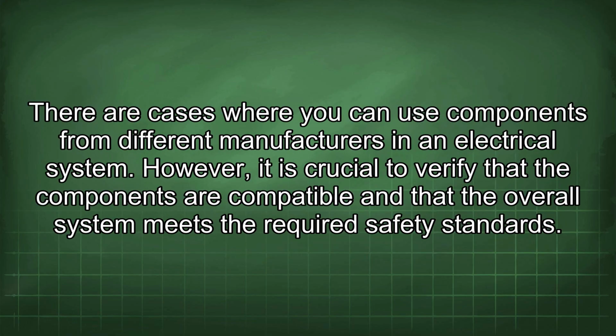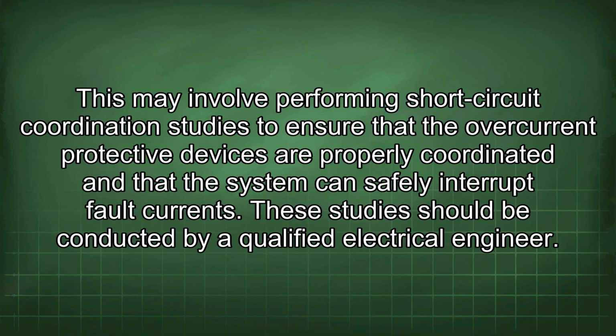There are cases where you can use components from different manufacturers in an electrical system. However, it is crucial to verify that the components are compatible and that the overall system meets the required safety standards. This may involve performing short-circuit coordination studies to ensure that the overcurrent protective devices are properly coordinated and that the system can safely interrupt fault currents. These studies should be conducted by a qualified electrical engineer.